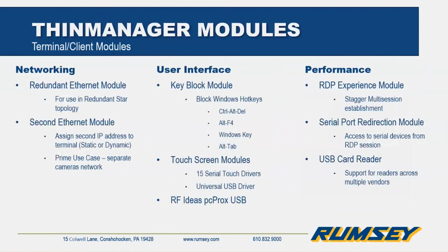Modules. This is probably the one takeaway that you can take from ThinManager if you're looking for a tip or a trick. Modules are how we grant capabilities to our Thin client hardware. So I said way back when that by default, a Thin client has the ability to recognize a keyboard or a mouse via USB, not anything else. But what if I wanted something else? What if I wanted to use that RFID badge reader, or add a thumbprint scanner or something along those lines? That's what the modules do. Think of them almost like drivers for Thin client.